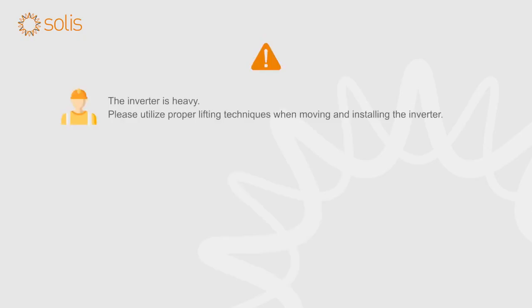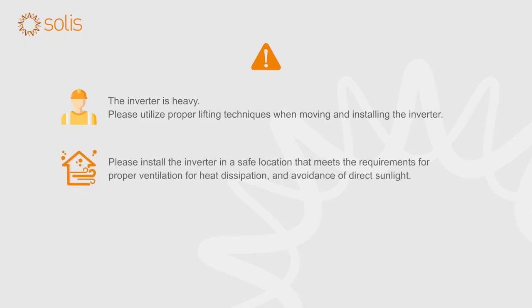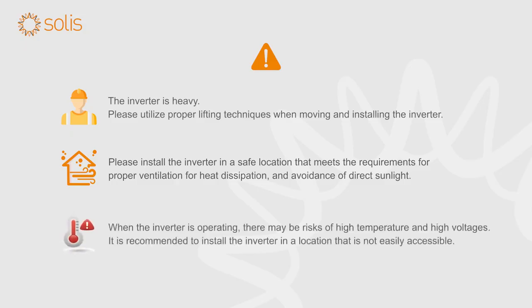The inverter is heavy. Please utilize proper lifting techniques when moving and installing the inverter. Please install the inverter in a safe location that meets the requirements for proper ventilation for heat dissipation and avoidance of direct sunlight. When the inverter is operating, there may be risks of high temperature and high voltages. It is recommended to install the inverter in a location that is not easily accessible.